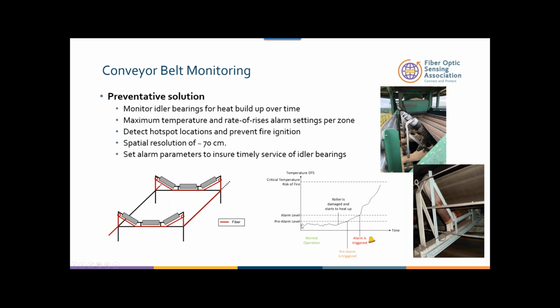What normally happens is you can monitor the temperature over time, and then if the temperature is increasing too fast, I give an example here in this picture, exponentially, you can set up alarms in a very, very strategic way. You have a pre-alarm that says, if you reach this temperature, something is wrong with the bearing. Send somebody to go there and check it out. The second approach is, if the temperature is going way, way too high, you can set an alarm.